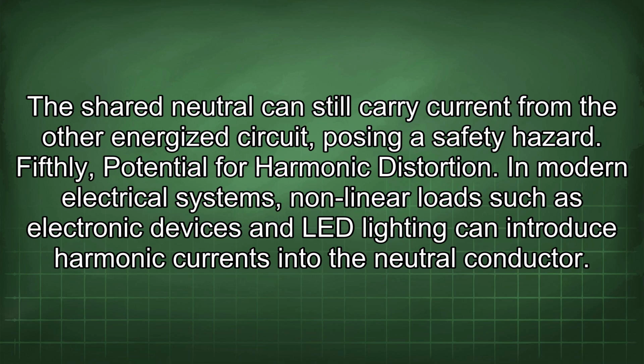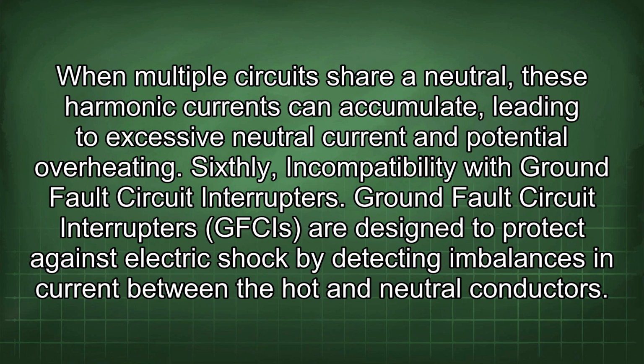Fifthly, potential for harmonic distortion. In modern electrical systems, nonlinear loads such as electronic devices and LED lighting can introduce harmonic currents into the neutral conductor. When multiple circuits share a neutral, these harmonic currents can accumulate, leading to excessive neutral current and potential overheating.